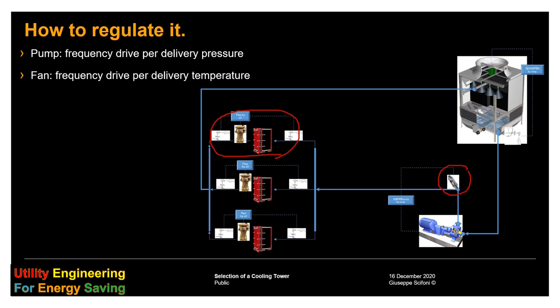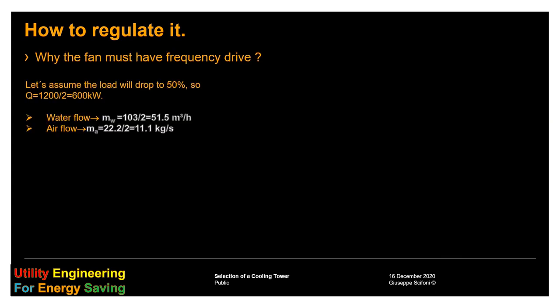What about the tower fan? Our suggestion is to use also here a frequency drive according to the delivery temperature of the water. Let's see why. Let's assume that the load drops to 50%. In this case, both the water flow and the air flow are becoming the half.